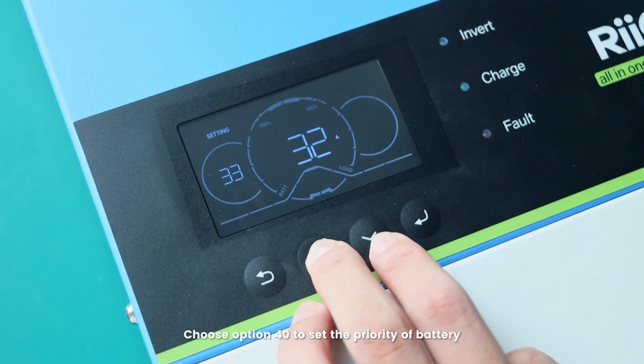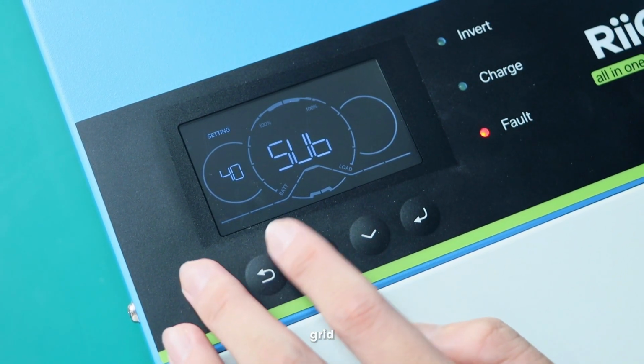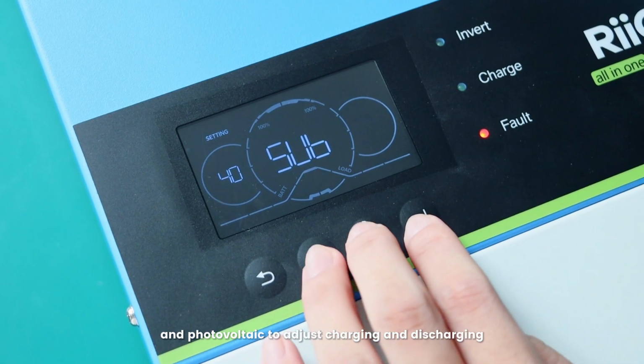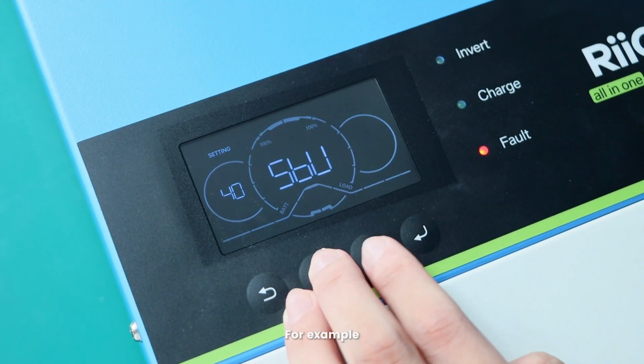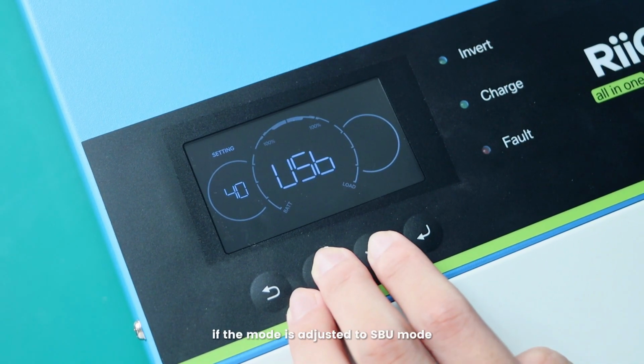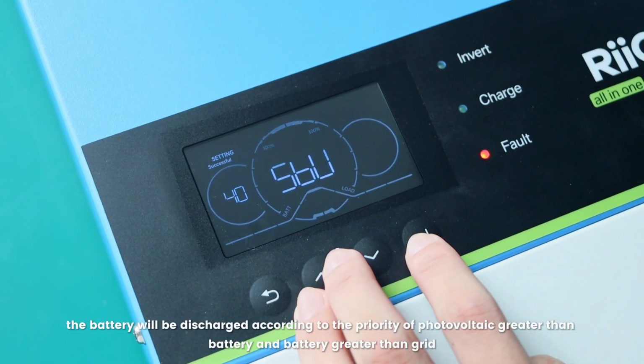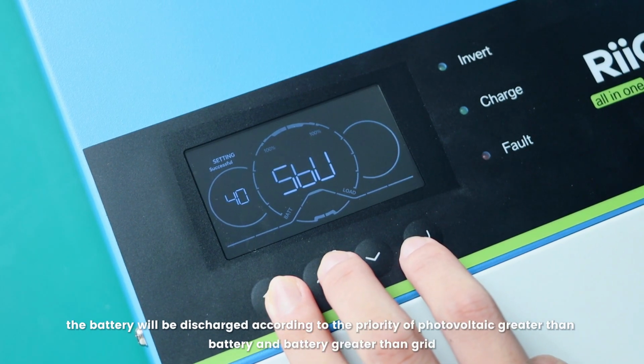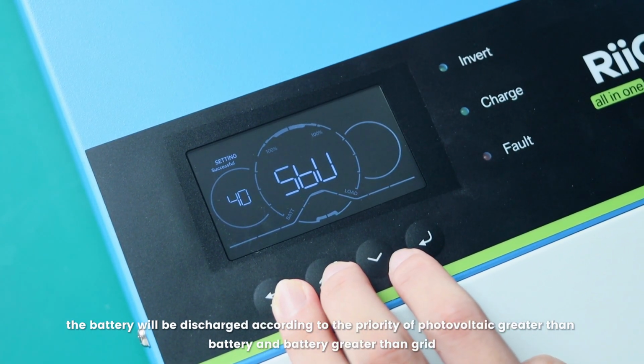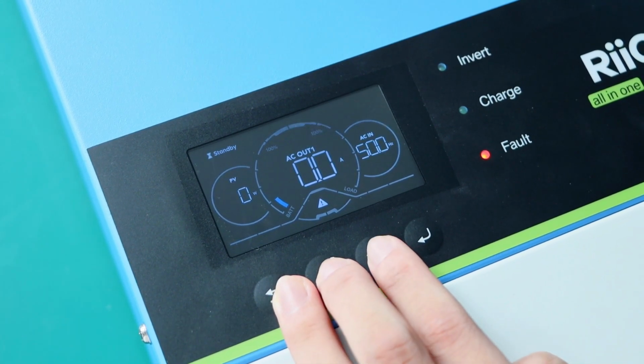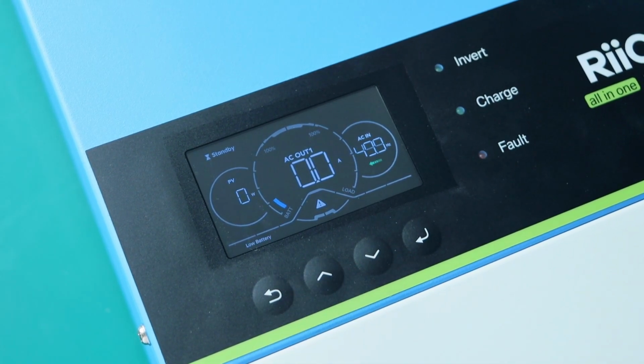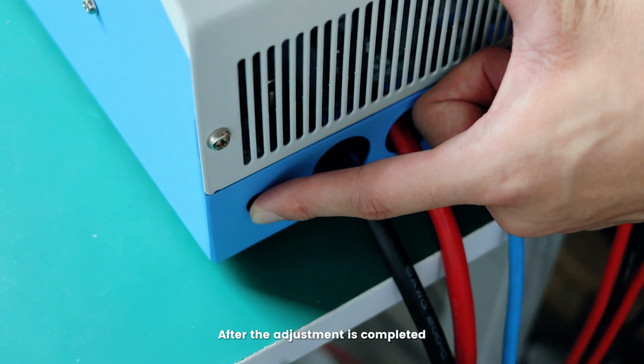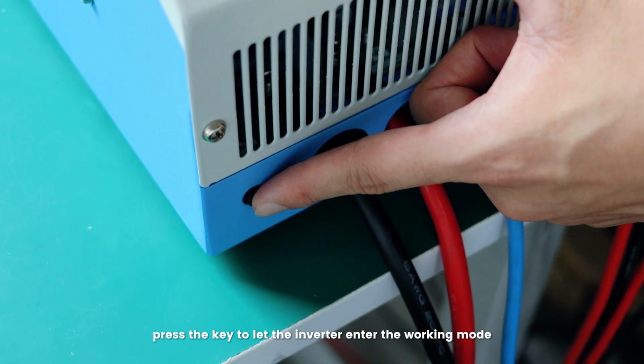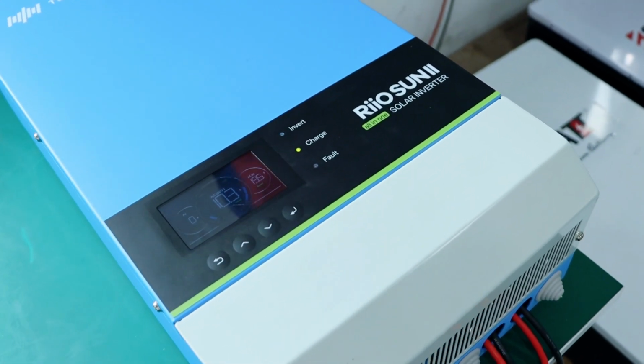Choose option 40 to set the priority of battery, grid, and photovoltaic to adjust charging and discharging. For example, if the mode is adjusted to SBU mode, the battery will be discharged according to the priority of photovoltaic greater than battery and battery greater than grid. After the adjustment is completed, press the key to let the inverter enter the working mode.